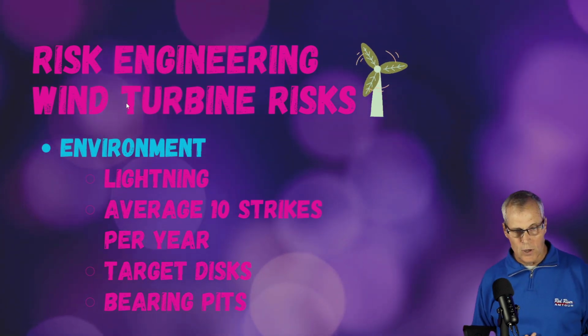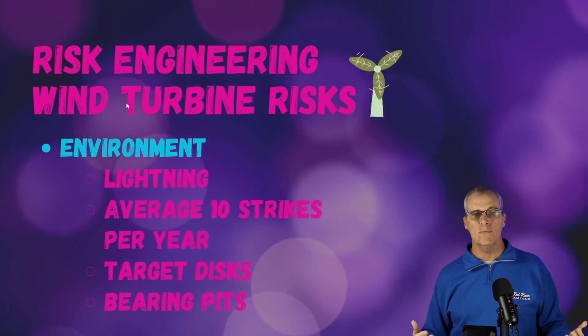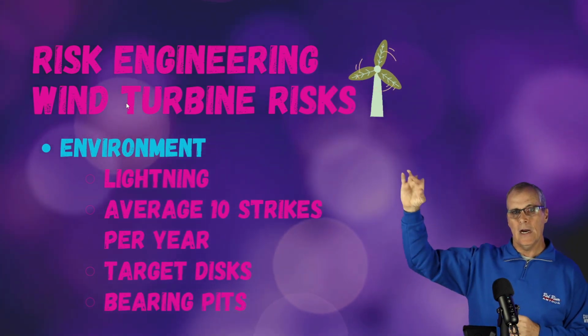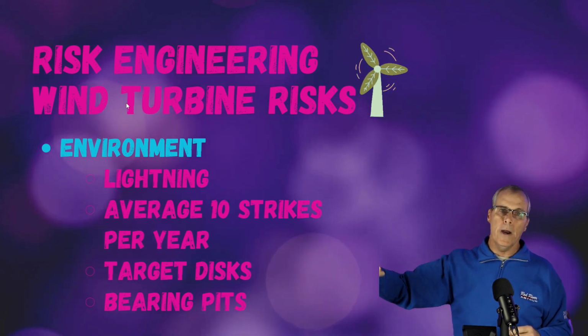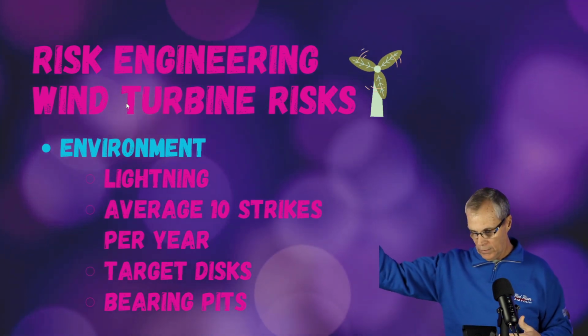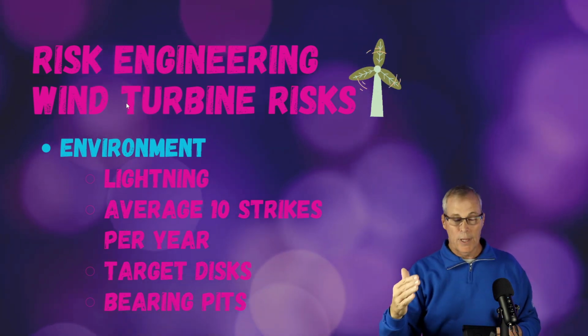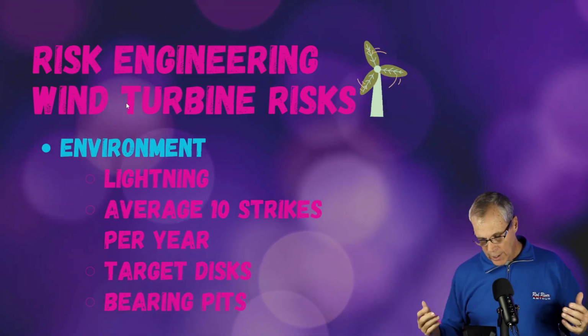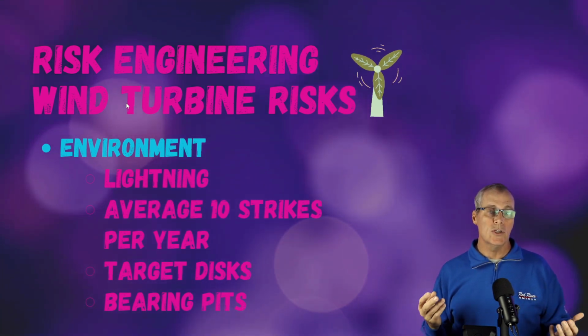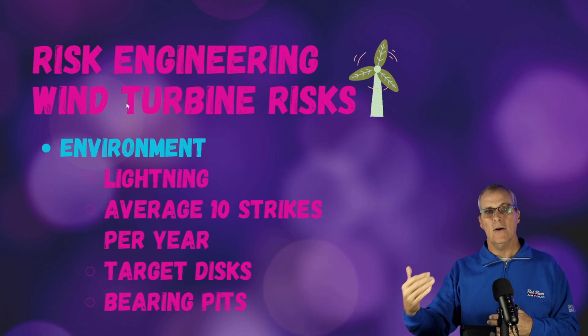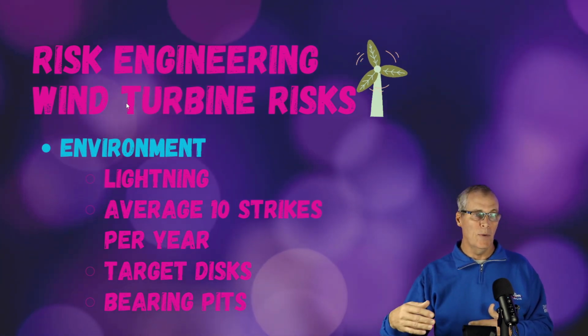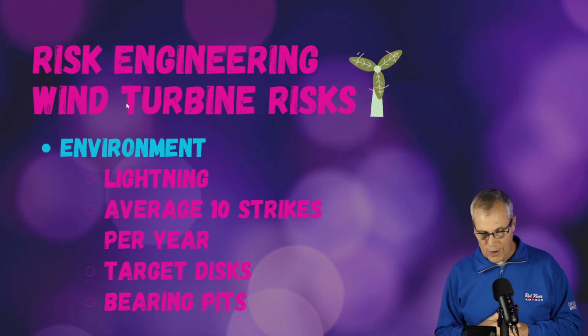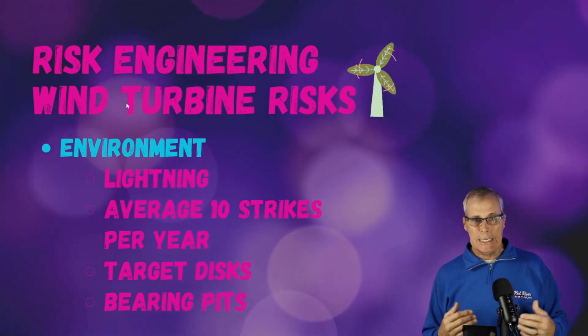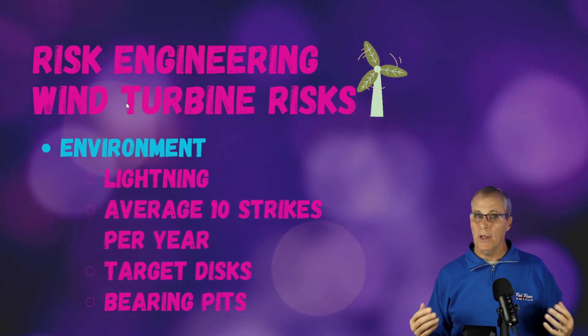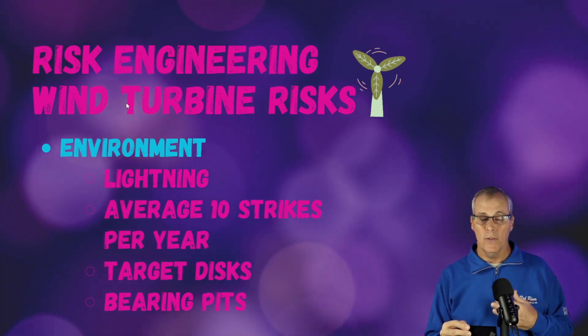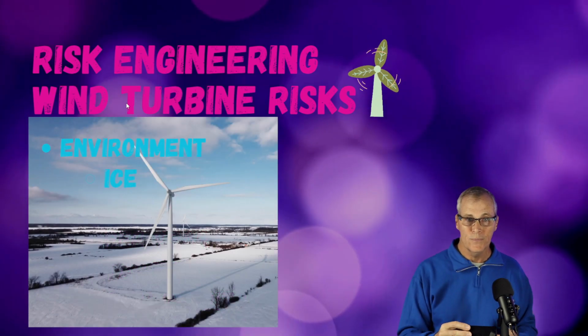But that is still one of the things that can cause them to fail. Some of the protection systems we see are target discs in the fiberglass blade with wire that bonds these discs, which are there to attract the lightning strike and hopefully take that current down to ground. Well, in order to get to ground, it has to go through the bearings, which can cause pitting. So we have to be careful about inspecting our bearings and making sure the bearing temperatures don't mysteriously start to rise after a thunderstorm. So lightning can be a challenge, but just be aware the industry has overcome the challenges pretty well.